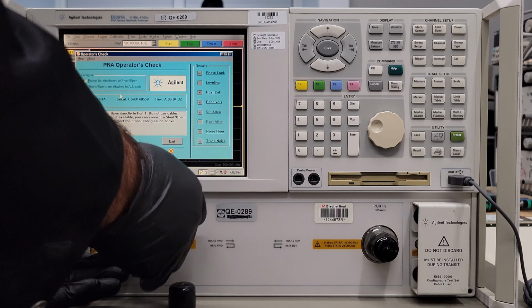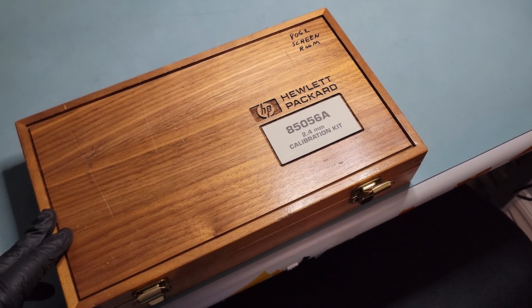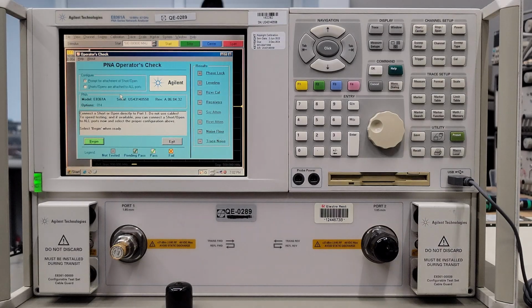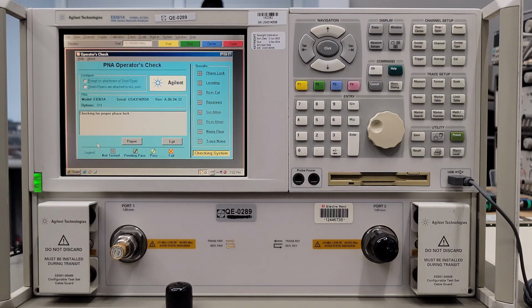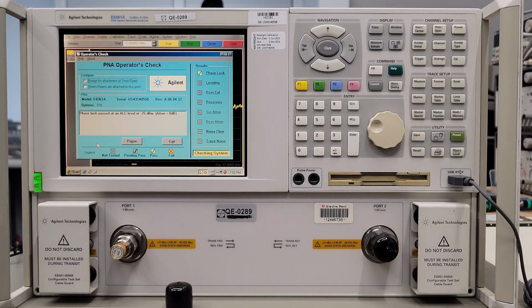To run the op check, we need to connect an open or short to the ports under test. The highest frequency standards I have are up to 50 GHz from my 85056A calibration kit. Hopefully these are good enough for a quick op check on this 67 GHz instrument.